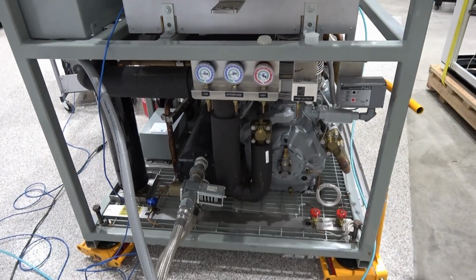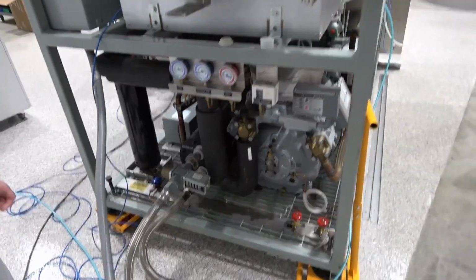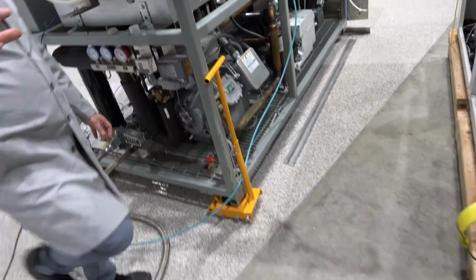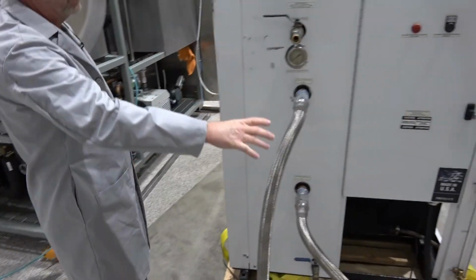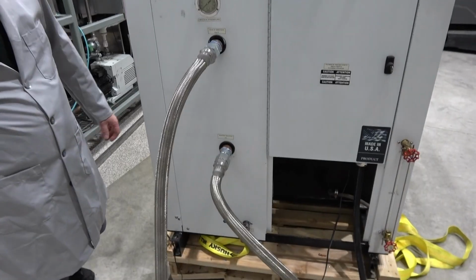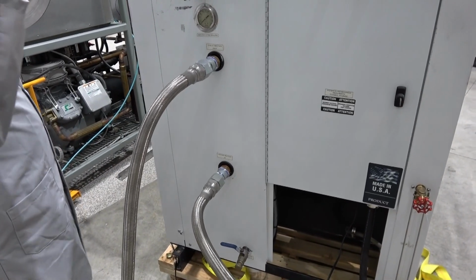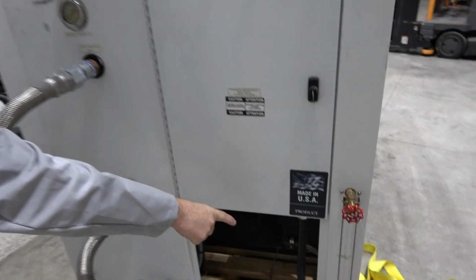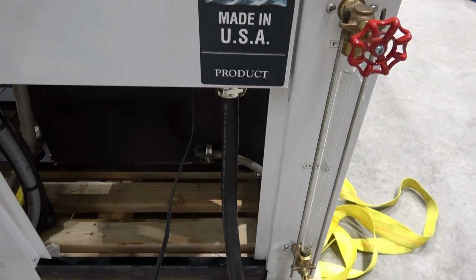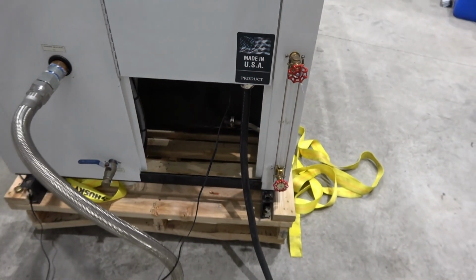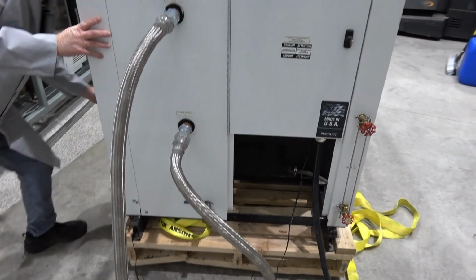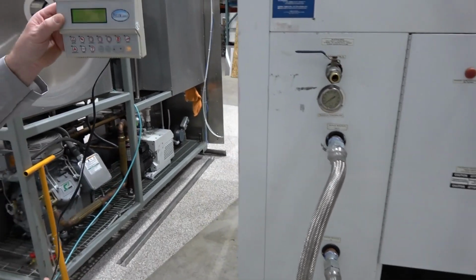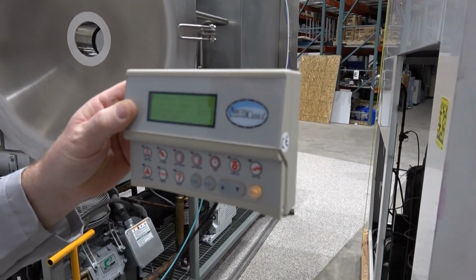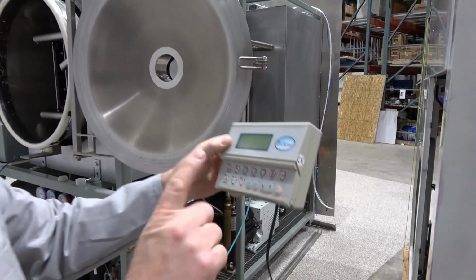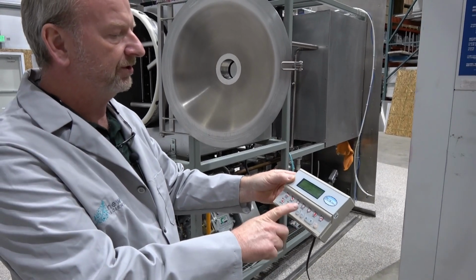We're just going to jump over to the chiller real quick here. We've basically got it plumbed in with some flexible lines going over to the system. This just needs a high voltage hookup—we've got our high voltage 30 amp line coming in here. The real nice thing about running this is it's just a simple control box that you would mount down close to your actual machine so you can just turn it on and off.